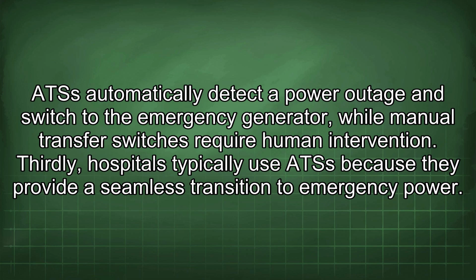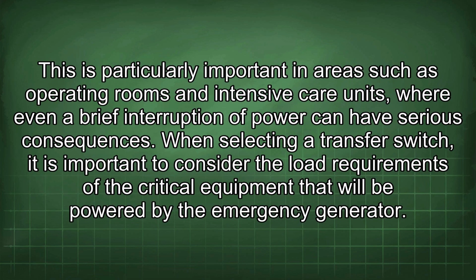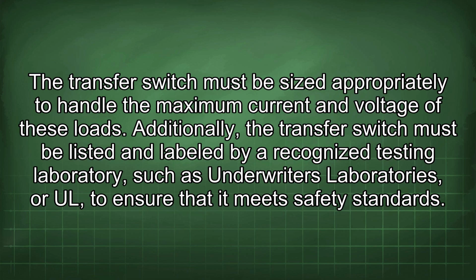Thirdly, hospitals typically use ATSs because they provide a seamless transition to emergency power. This is particularly important in areas such as operating rooms and intensive care units, where even a brief interruption of power can have serious consequences. When selecting a transfer switch, it is important to consider the load requirements of the critical equipment that will be powered by the emergency generator. The transfer switch must be sized appropriately to handle the maximum current and voltage of these loads.